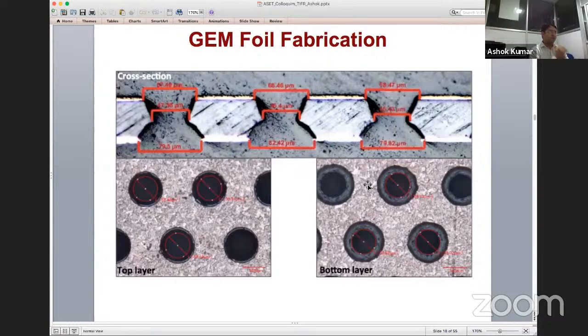Okay, so this is the actual image of the GEM foil. As I have told, this is the cross-sectional view where you can see the inner hole and the outer holes. Then there is a layer of the holes. You can see the top layer of the single mask foil and the bottom layer of the single mask foil, and you can see the difference in the etching also. The bottom layer is not that well etched, and the hole size also differs, by about 20%. But after all, the effect on the GEM performance is not much, which is really a good thing with this detector.